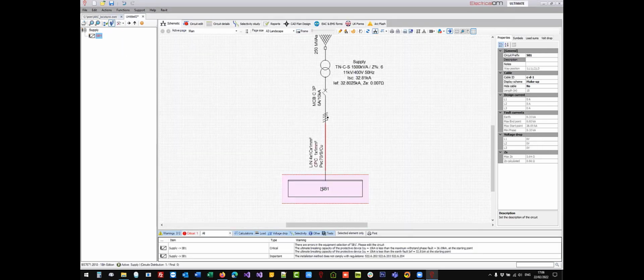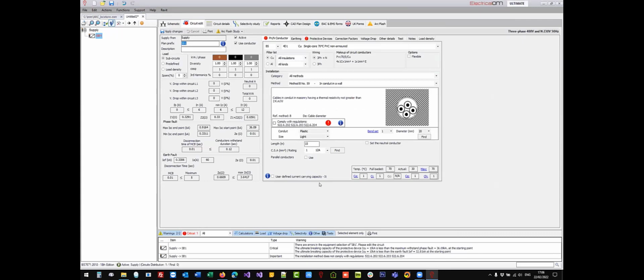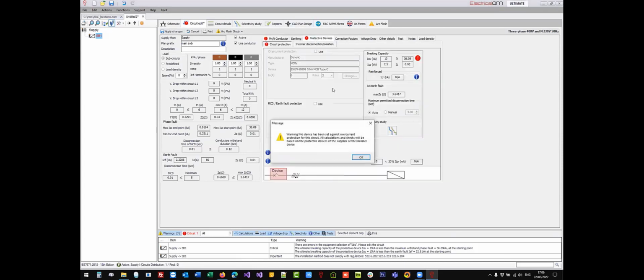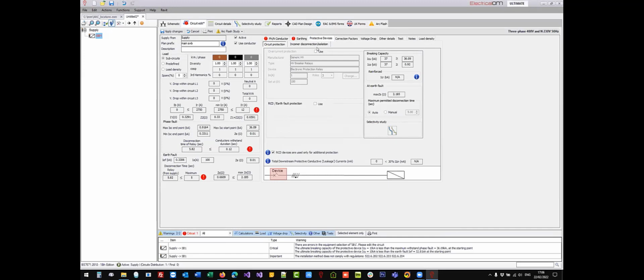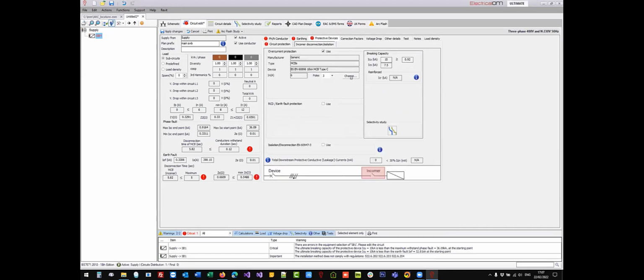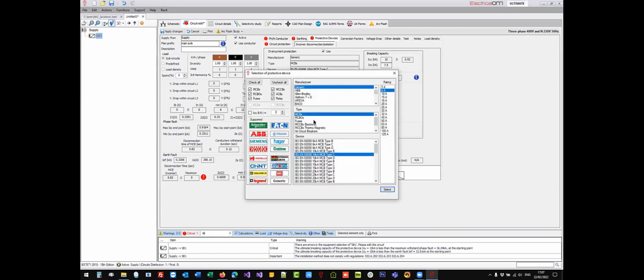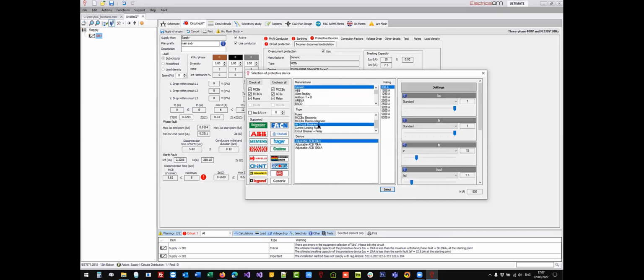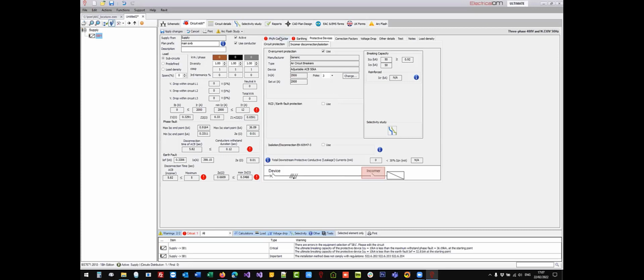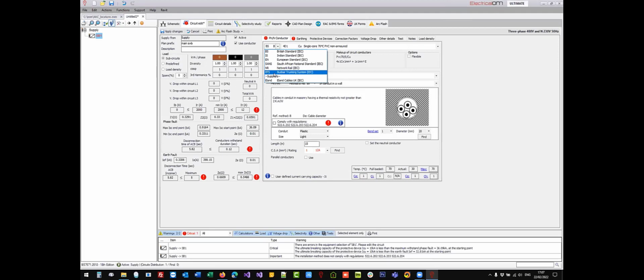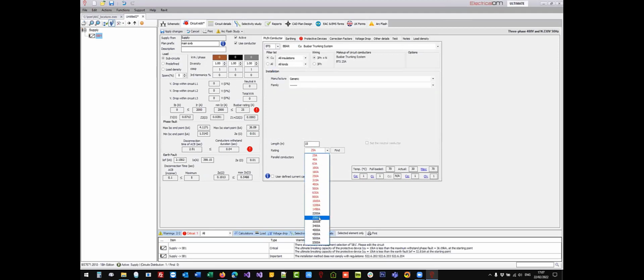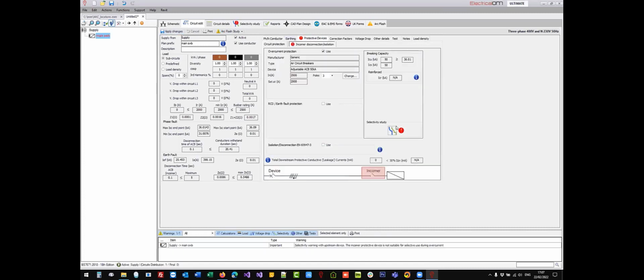So go back to this new project. I will access my main switchboard. Okay, so let me call it main switchboard. And then on the protective devices, I will uncheck to use a device at the starting point, and I will use an in-cabinet device here, an overcurrent protective device, which I will change to an air circuit breaker. Okay, so I'll choose generic for this example. And then I will size my conductor. I will choose a bus bar, like in the previous show. I'll use 2,500, just 5 meters. And after applying this change, I can see that there is a problem with my selectivity study.